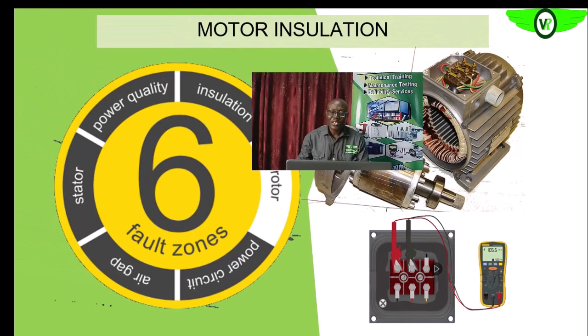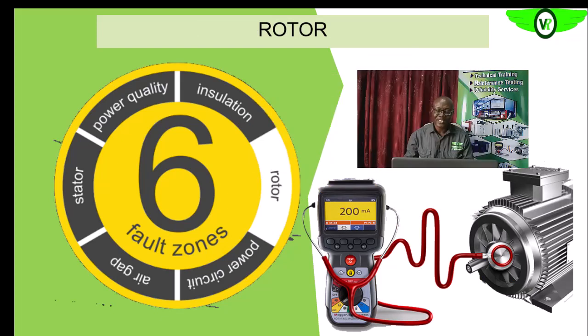Okay, so the insulation fault zone is another area that we need to look at, because a failing insulation will affect the reliability of the entire electric motor system. Then we also want to look at the rotor fault zone. Remember, as we discussed earlier in this section, the field generated in the rotor interacts with the field generated in the stator. So anything that affects that field will affect that interaction. What happens is that the efficiency of the electric motor will be affected. Okay, so that is what we actually do here.